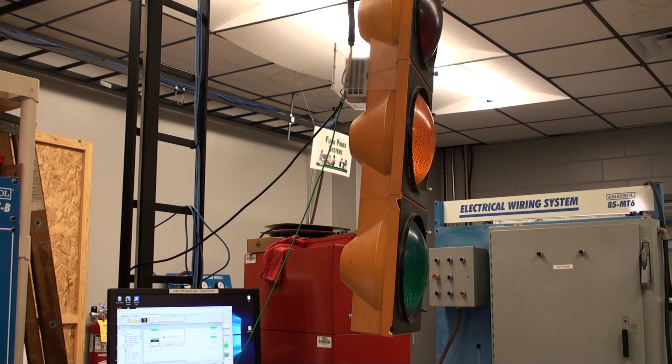So I figured it was an address problem, or an actual output blown, and in this case it was a blown bulb. And the other thing, I had addresses swapped. So basically the way I had it set up, when I was pressing the red button, green was coming on. When I was pressing the green button, red was coming on.